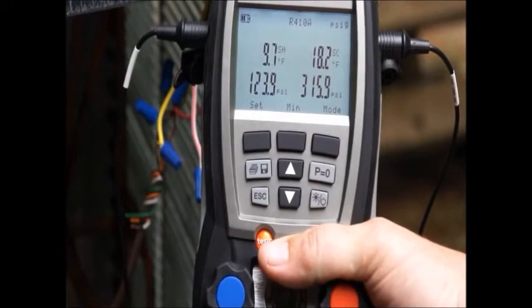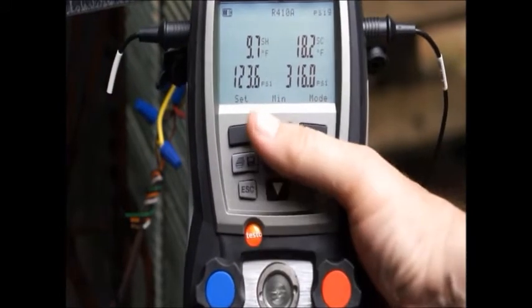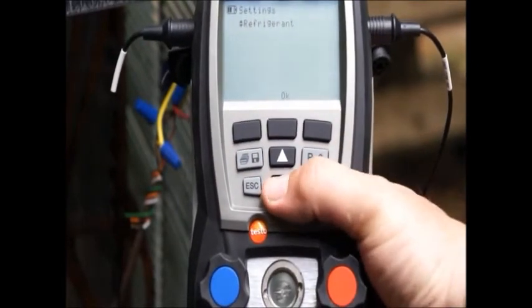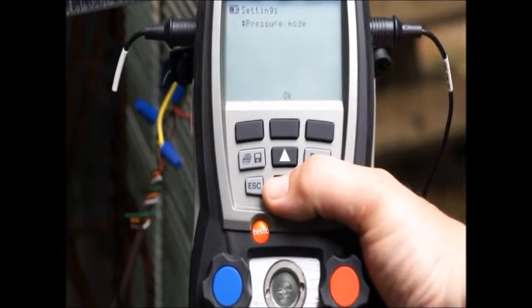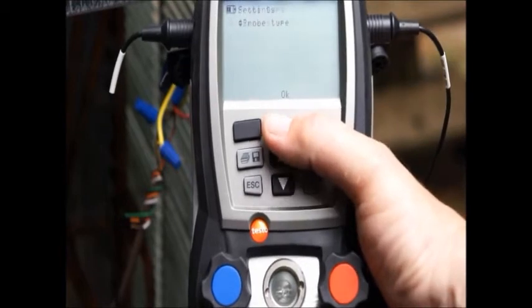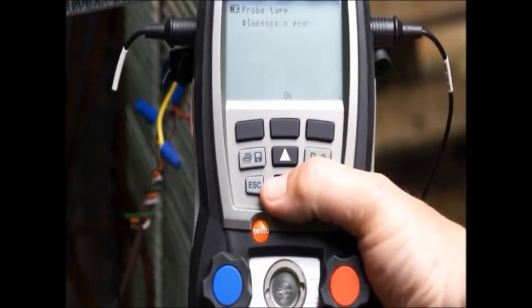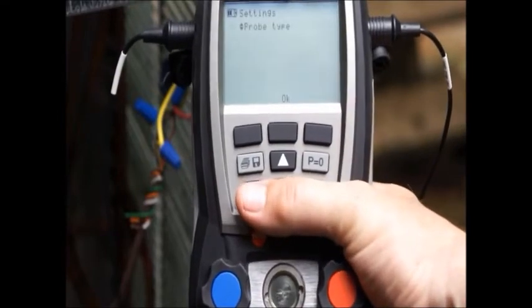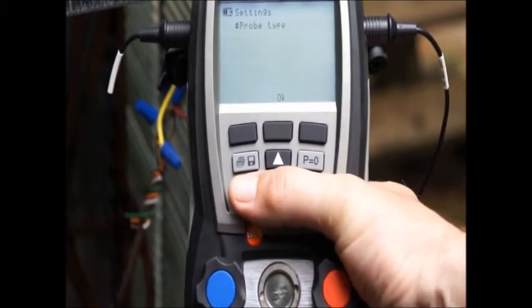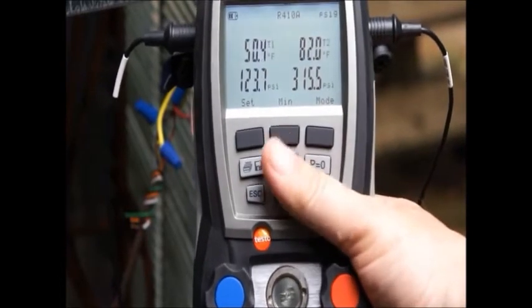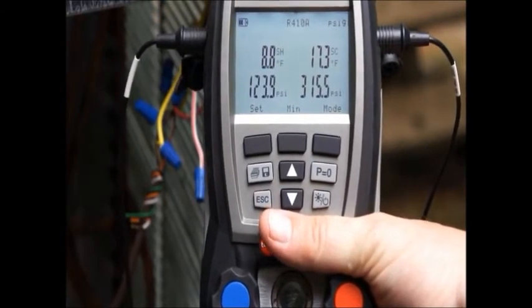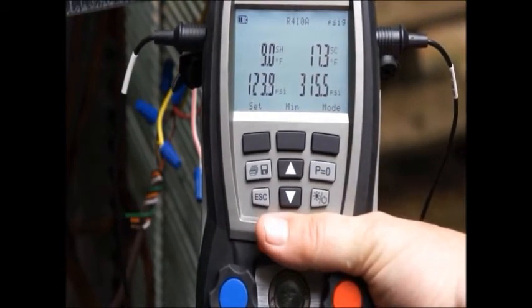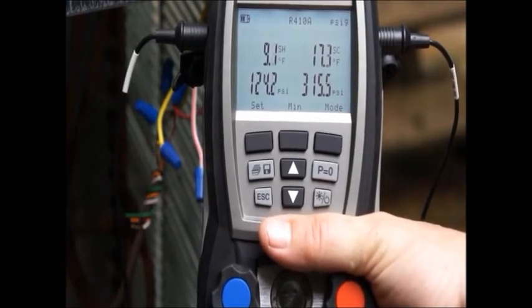The other thing we need to do is make sure our probes are set up correctly. I'm going to go into settings, scroll down until I see pressure mode, vacuum, measuring, date, time, language, probe type. I need to change this from immersion probe to a surface probe and hit OK because there's an offset for temperature built into the machine. What that's going to do is compensate for the outdoor air temperature and offset those probes by probably a couple of degrees, which increases the accuracy of the instrument.